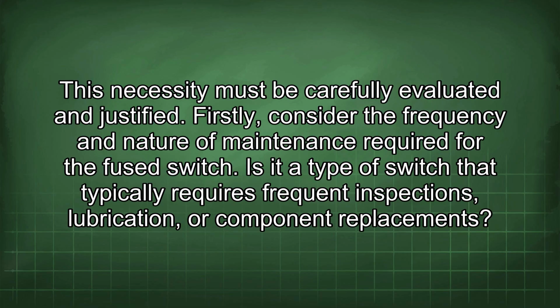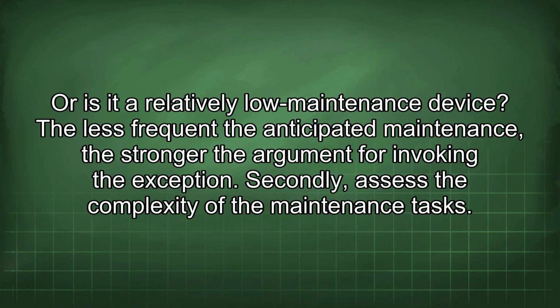Firstly, consider the frequency and nature of maintenance required for the fuse switch. Is it a type of switch that typically requires frequent inspections, lubrication, or component replacements? Or is it a relatively low-maintenance device? The less frequent the anticipated maintenance, the stronger the argument for invoking the exception.